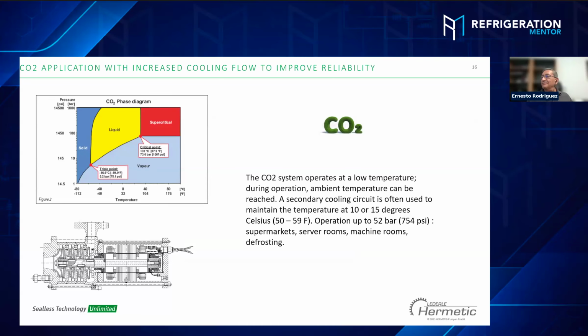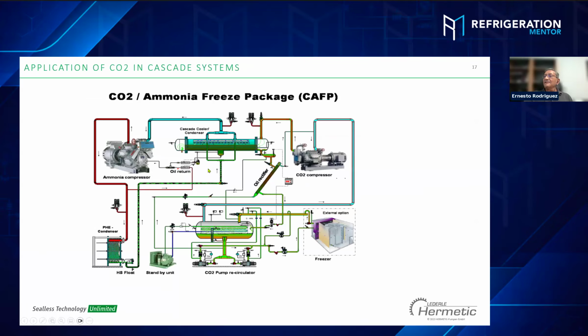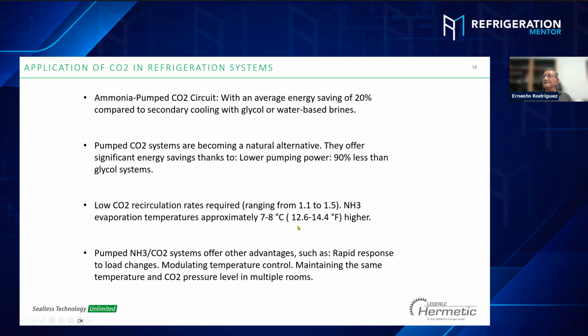Okay, let's go back to the CO2. Basically, we have a pump for CO2. 52 bars is the most standard capacity, between 50 to 59 Fahrenheit, or 10 to 15 degrees Celsius. This is the typical installation for a cascade system. We have the CO2 pump plus the ammonia. I see lots of these applications now. We have ammonia on the top side to lower the ammonia charge, and then we have CO2 pumping through the facility. What is the advantage we have with this cascade system?